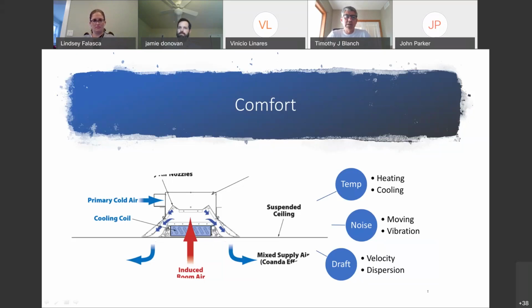The biggest problem you can have with chilled beams is raining. You didn't control your dew point, you introduced too cold of chilled water, and it sweated, and your beams are raining. We've never had that happen. But the thing about an active chilled beam is that it needs primary cold air. In this case, you see that on the side, primary cold air, and you sort of prime the pump. It goes through the nozzles up top, and the high velocity, low pressure helps induce room air across the coil, mixes with the primary air, and you get about a 3-to-1 induction ratio and increase the heating and cooling performance of the beam.